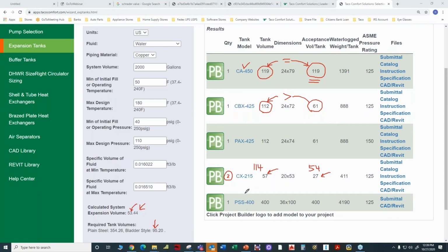Now, when we come to plain steel tanks, they are typically not used in new designs today, although we have seen a couple here and there. Generally, they're part of the replacement market. Years ago, people used to use plain steel tanks. And if you'll notice, the plain steel tank over here on the left side has to have a minimum volume of 354 gallons, so the software selected this one. So you can see how much bigger the plain steel tank needs to be, almost 4 times bigger than the bladder style tank.